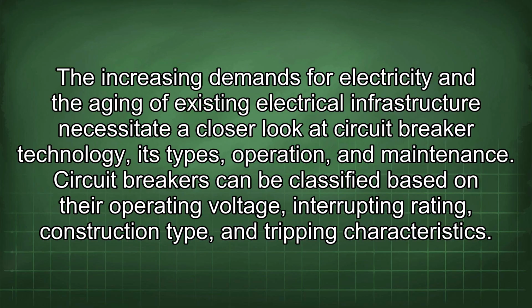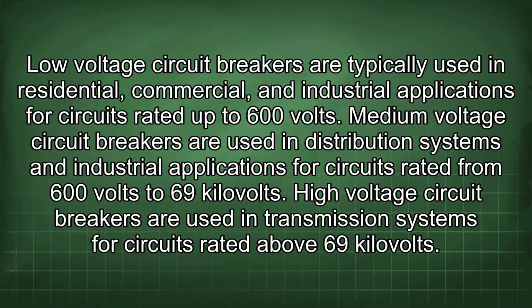The increasing demands for electricity and the aging of existing electrical infrastructure necessitate a closer look at circuit breaker technology, its types, operation, and maintenance. Circuit breakers can be classified based on their operating voltage, interrupting rating, construction type, and tripping characteristics. Low-voltage circuit breakers are typically used in residential, commercial, and industrial applications for circuits rated up to 600 volts. Medium-voltage circuit breakers are used in distribution systems and industrial applications for circuits rated from 600 volts to 69 kilovolts. High-voltage circuit breakers are used in transmission systems for circuits rated above 69 kilovolts.